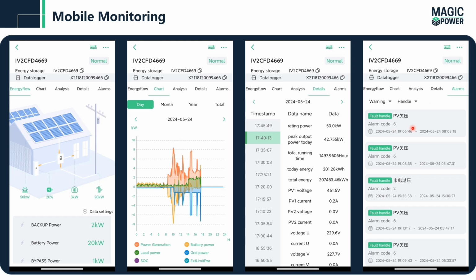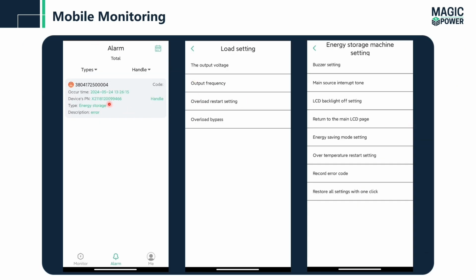If there is any alarm or warning or error in the system, we can see here what kind of alarm there is. So here will be a list. Further moving into the fault and alarm, we can see the occurrence time and the type, and the description of that warning or alarm or error. In the description we can see the code for that alarm or error, and here we can see the status, whether it is handled or not. On the load side we can set the output voltages and frequency. Similarly, if we look at the energy storage machine setting, basically these are settings for the machine itself.